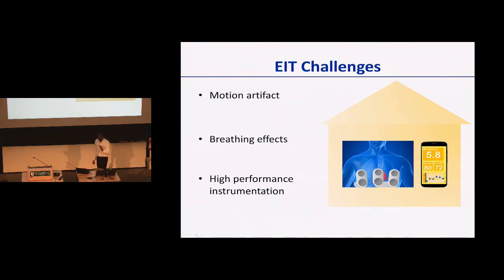Now, if we try to do this with a linear circuit design, we'd end up with an instrumentation box that consumed several watts of power. That power has to be dissipated as heat, and because of patient safety, we'd have to keep the instrumentation off to the side and run relatively long cables from the electronics to the electrodes on the patient's chest.